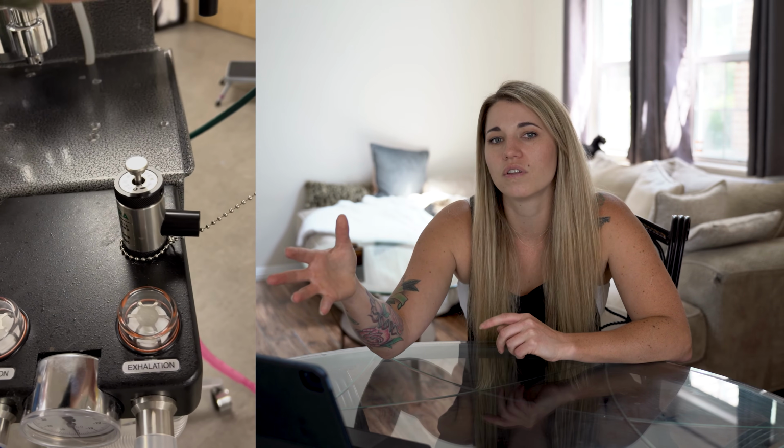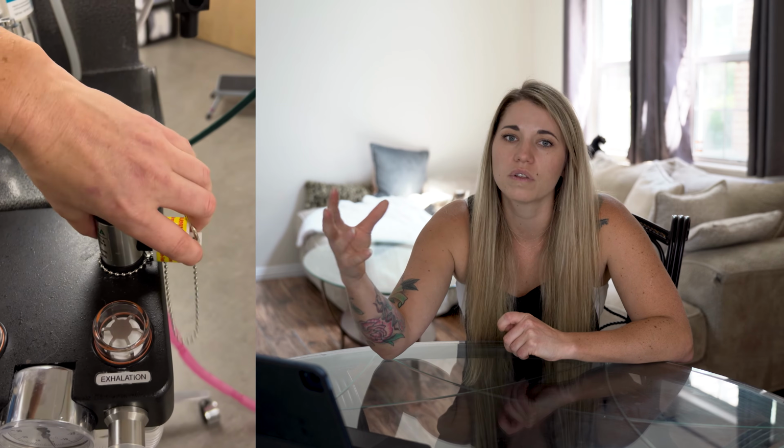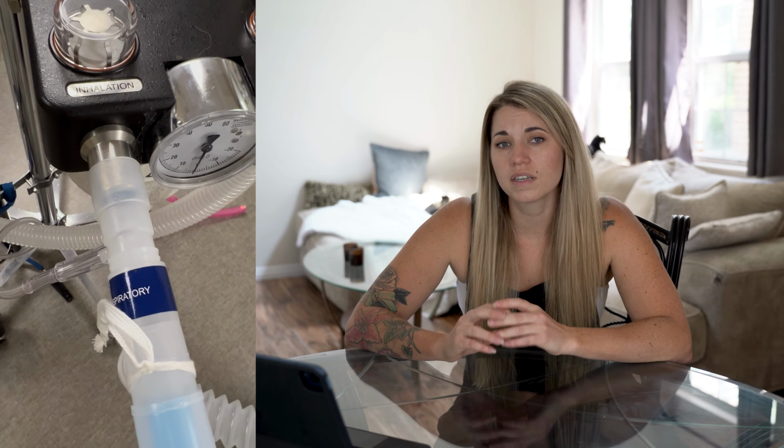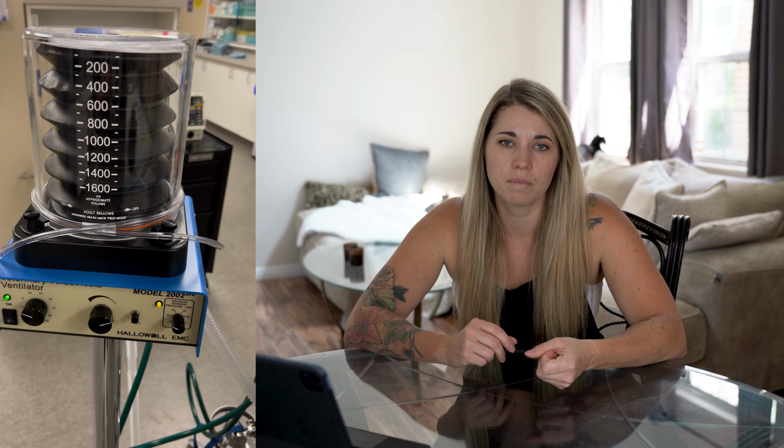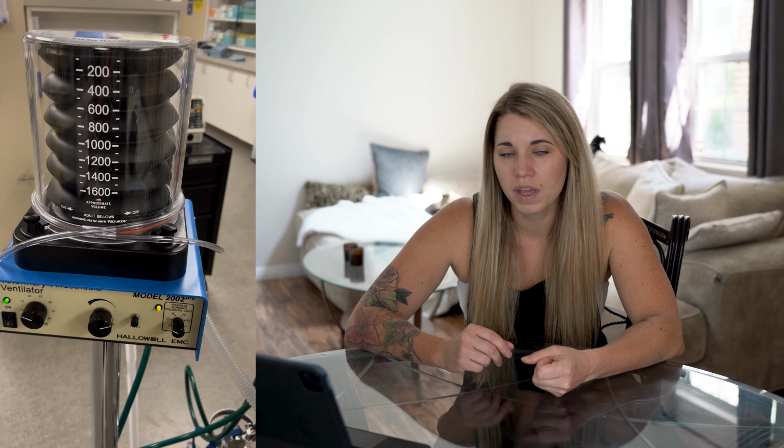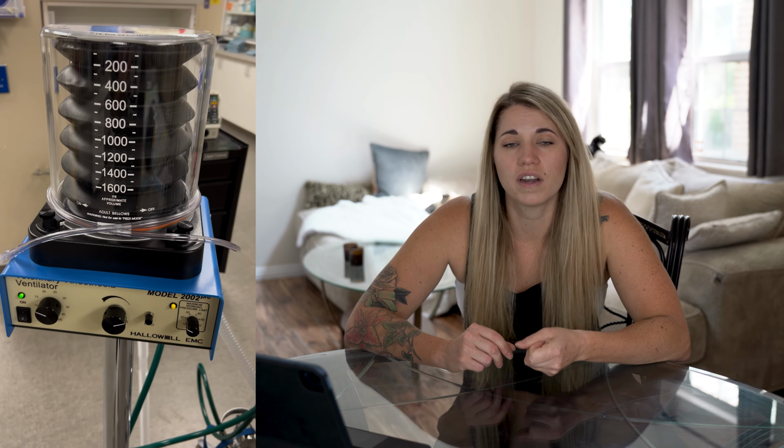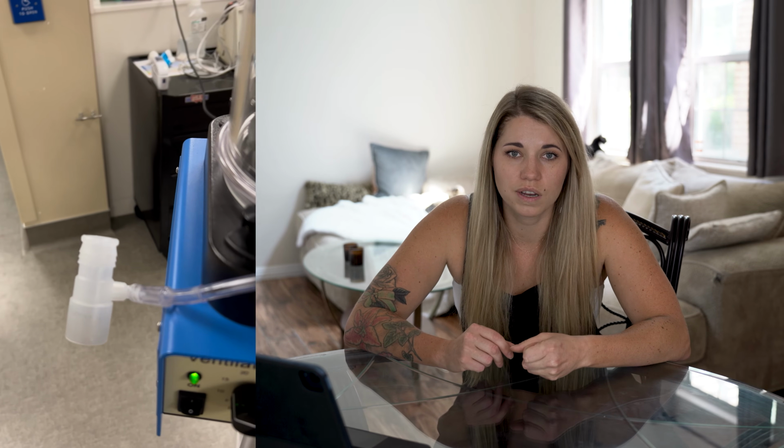If your anesthetic machine has a safety valve, such as the Superior valve, you do need to make sure that you have the valve blocker appropriately attached. Otherwise, you will not be able to fully ventilate your patient. Your ventilator will think there's a leak in your system. Next, ensure your exhaust hose is connected to the scavenging unit. And then next, connect your pressure sensor T before the inspiratory limb of your patient breathing circuit. If you forget this step, your ventilator will be alarming the second you turn it on.